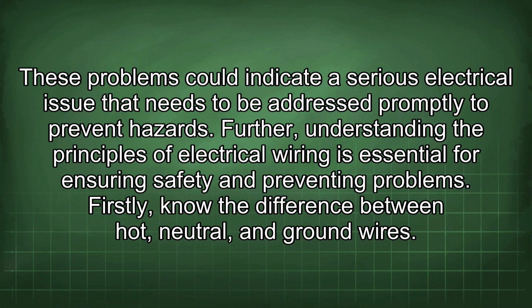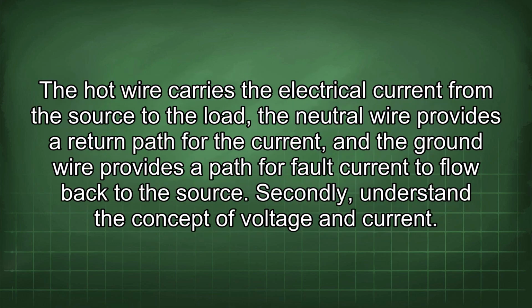Further, understanding the principles of electrical wiring is essential for ensuring safety and preventing problems. Firstly, know the difference between hot, neutral, and ground wires. The hot wire carries the electrical current from the source to the load. The neutral wire provides a return path for the current, and the ground wire provides a path for fault current to flow back to the source.